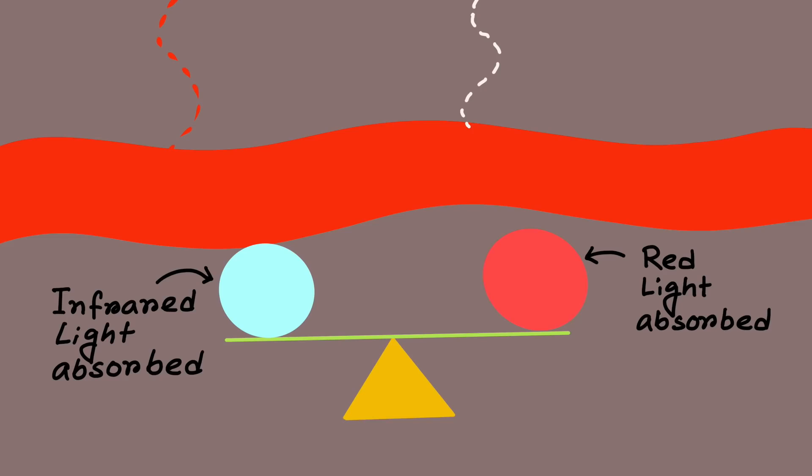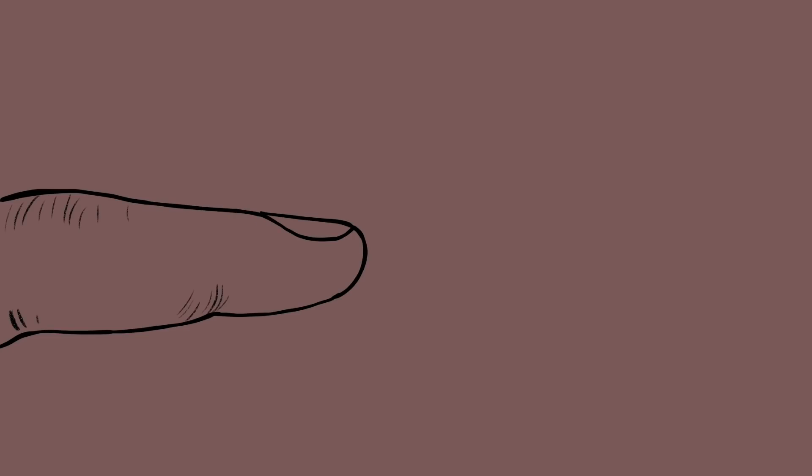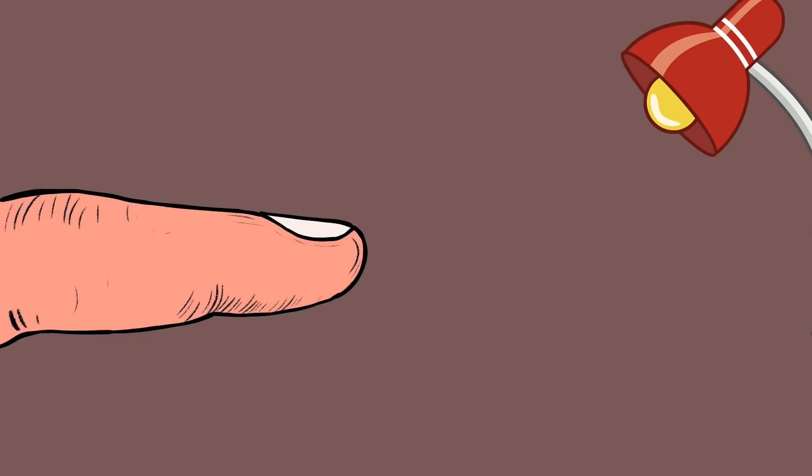Using this ratio, the pulse oximeter can then work out the oxygen saturation. The internal circuits and the processing components of the pulse oximeter do some calculations as well.